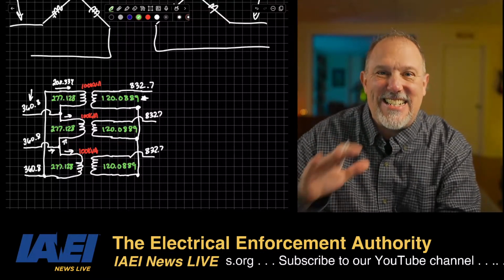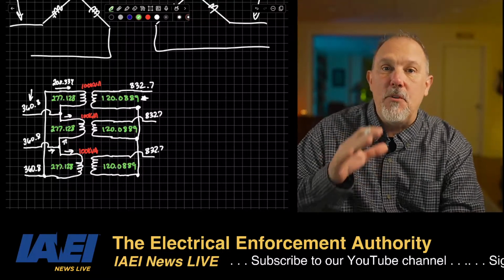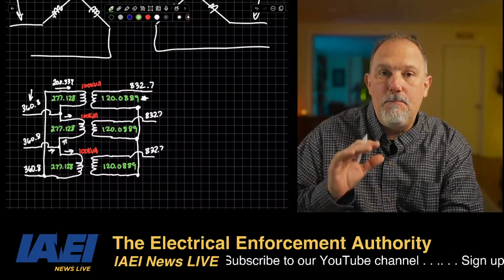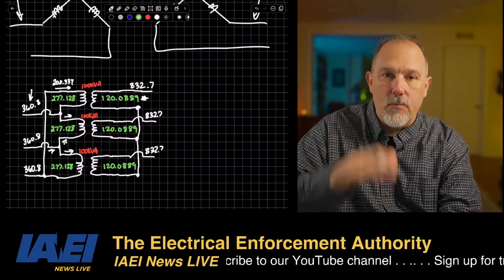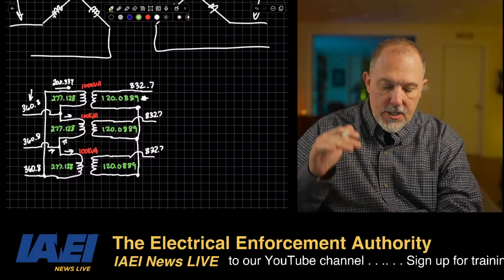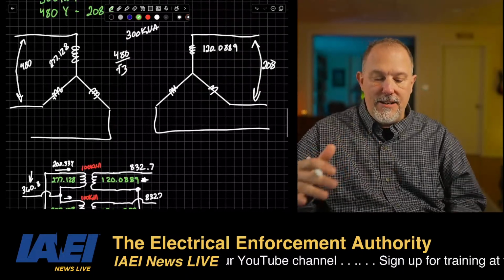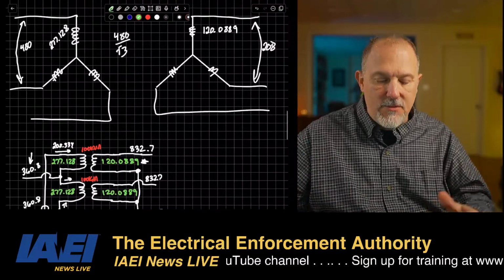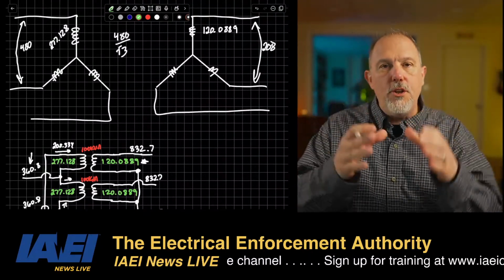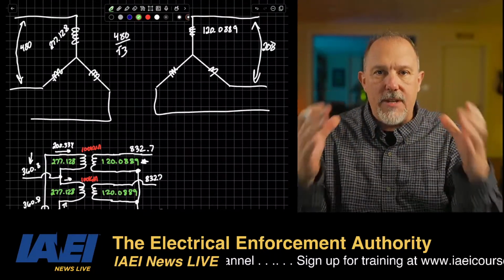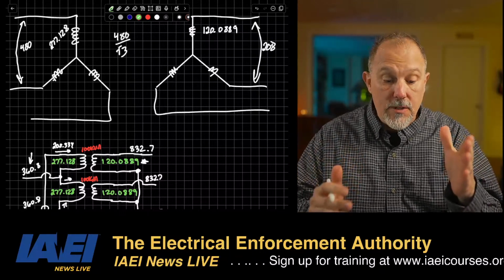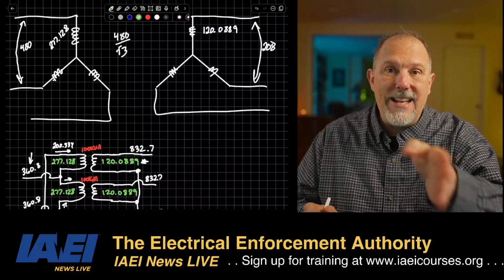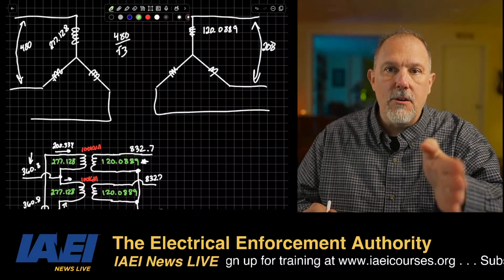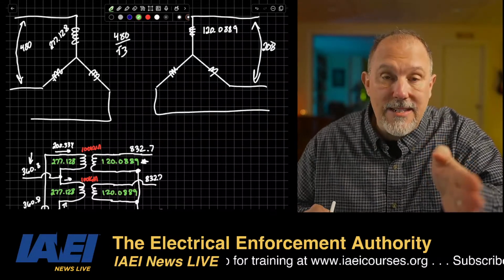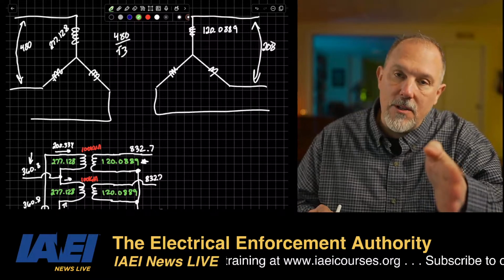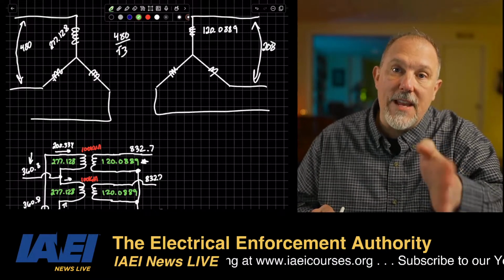I know, it's exactly right. And that's why people think it's wrong. But it's not, because of that square root of freaking 3. So now I've just done this in YY instead of delta delta, but you've got to understand what your voltages are and where you're measuring them. If you establish 480 as the number, then your line to neutral is not 277. It's 277.128 because of that square root of 3.